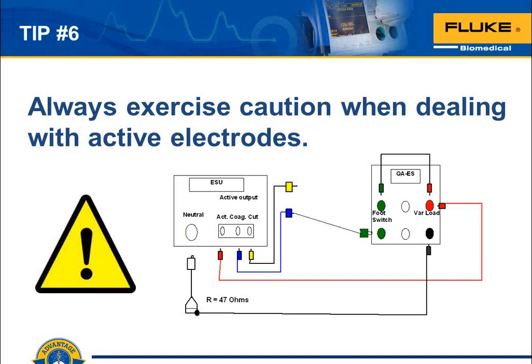Now, in this case, there's an internal foot switch in the ESU analyzer so that when you press start, the ESU analyzer itself is what engages the electrosurgery unit and causes it to energize. So you can actually get your testing done very quickly that way. It's not the only way that you provide these hookups. You can do a more simplistic two connection approach and use the ESU's own foot switch. Really, either one of those. Just be sure you're using banana test leads and you're making those connections completely and properly. No exposed metal on your test leads, no exposed metal. You really want to reduce all of that risk to yourself or to your junior technicians.